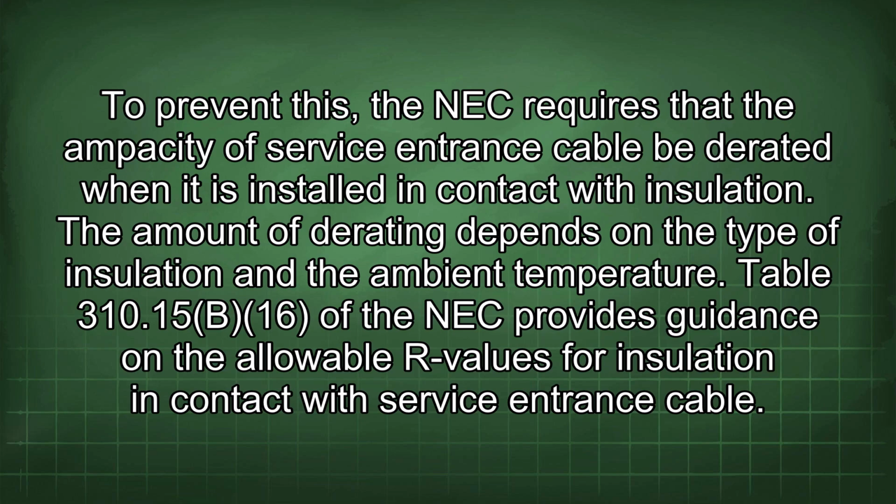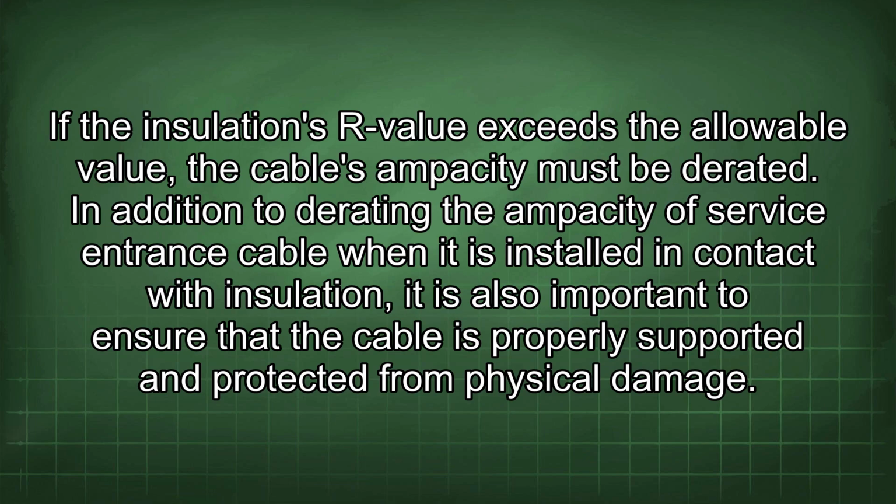Table 310.15(B)(16) of the NEC provides guidance on the allowable R values for insulation in contact with service entrance cable. If the insulation's R value exceeds the allowable value, the cable's ampacity must be derated.